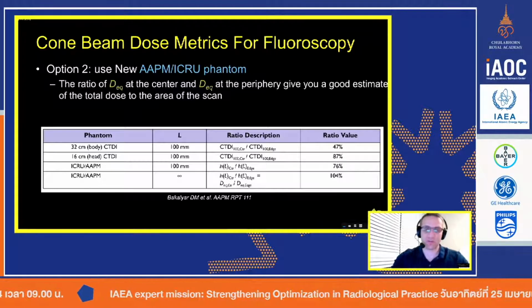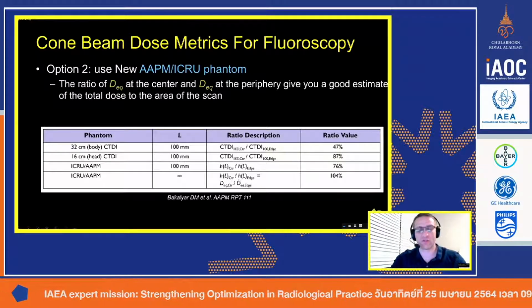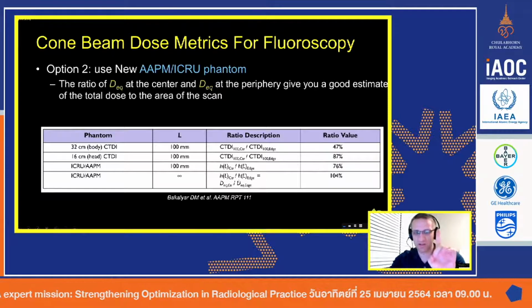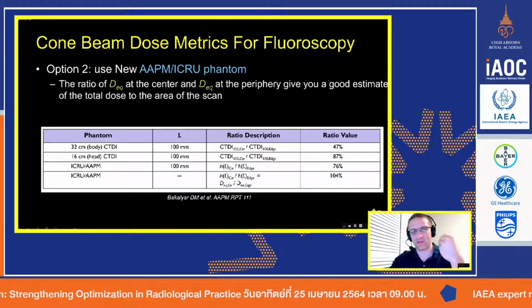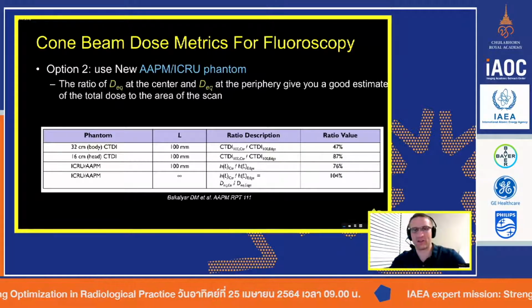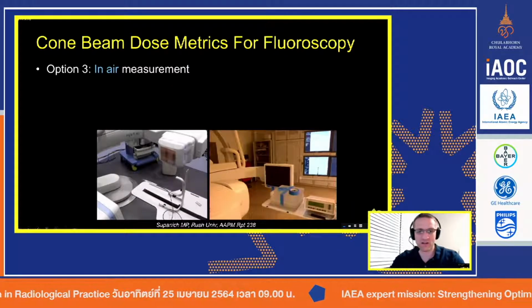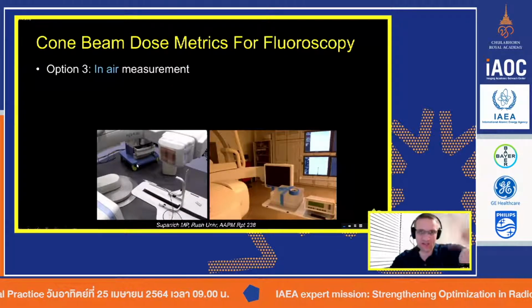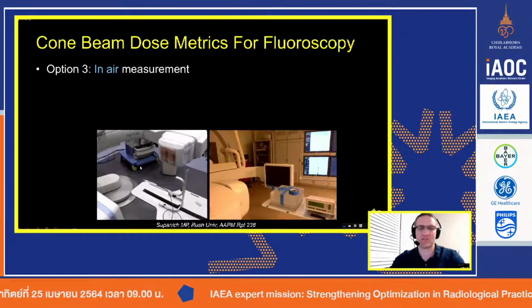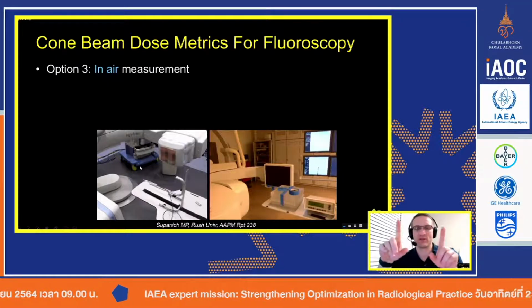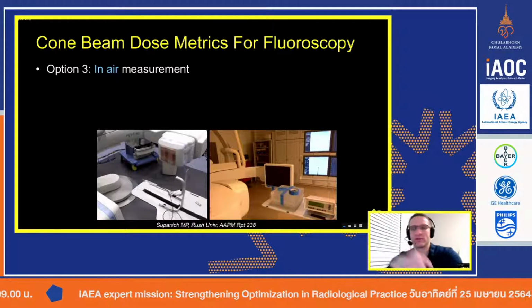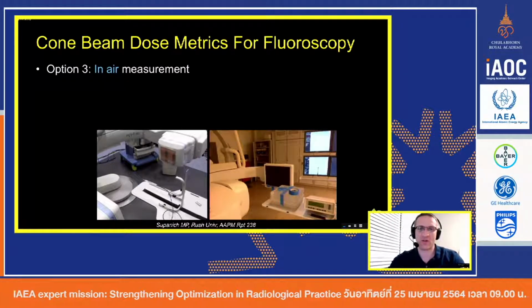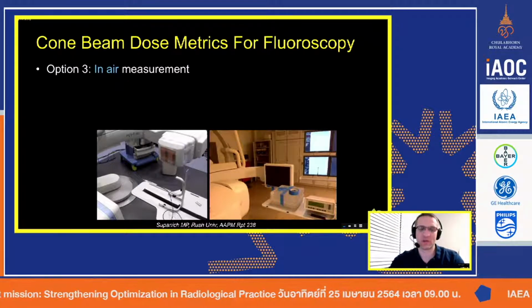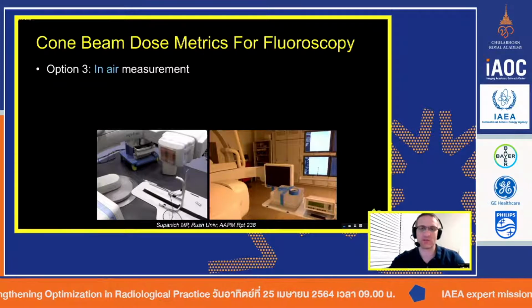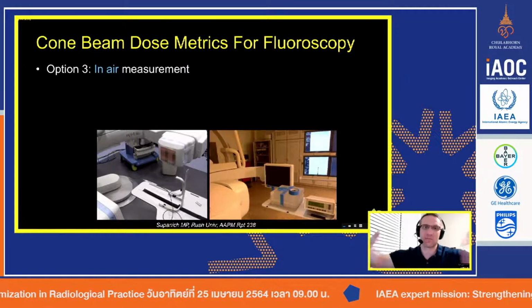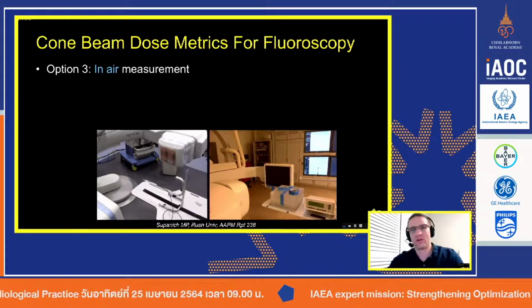What you typically will do is you'll go to all this trouble with the phantom once. And then once you take that phantom off, you'll place the ion chamber in air in between the two, and you'll do the same spin, and you'll take the ratio of those in air measurements versus the equilibrium dose measurement. And now you have a correction factor. So the next time you come, when you have to do these measurements next year, you don't need to lug that big 67 pound phantom everywhere.